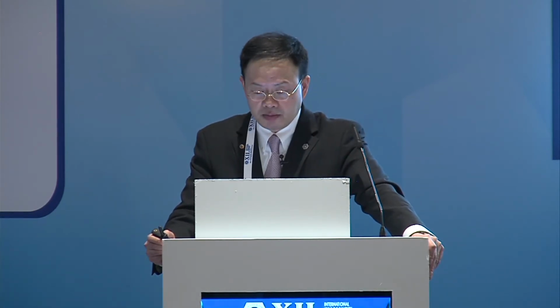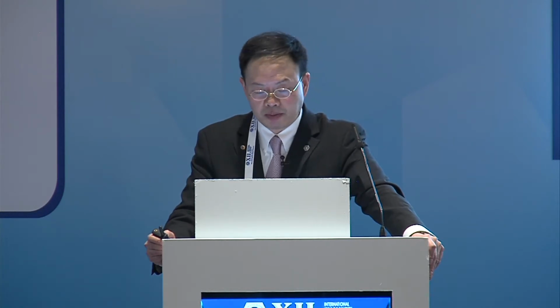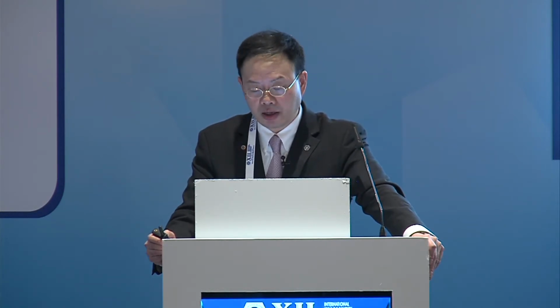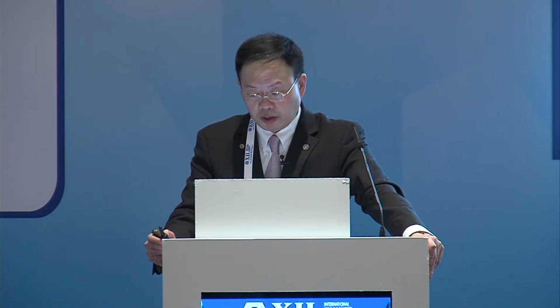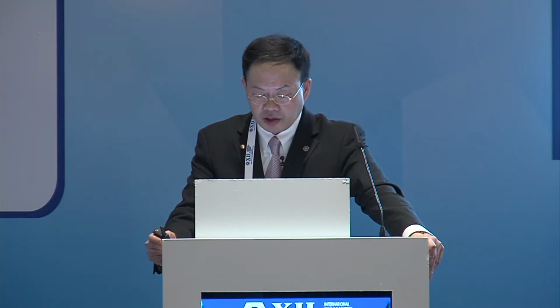Operating room. Typically, operating rooms we design in positive pressure. The pressure could be 2.5 to 8 Pascal. That's actually very low, very minimum. Some designs use much higher pressure differential. And HEPA filter is typical, and UVGI light. Also the velocity requirement in the US typically is 0.3 to 0.5 meter per second.